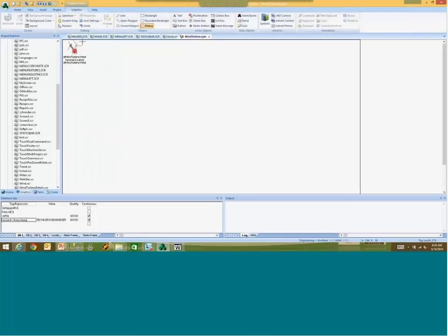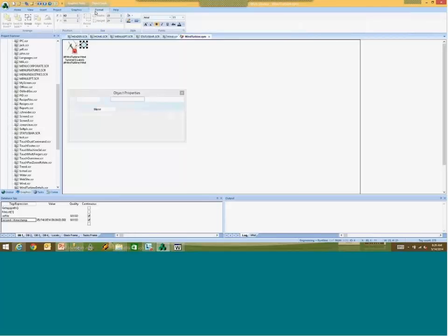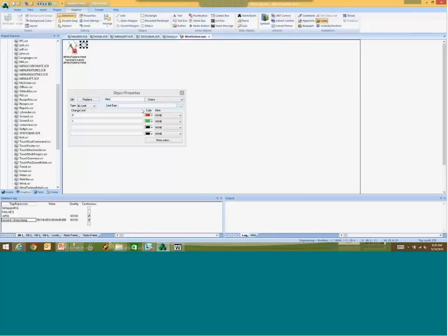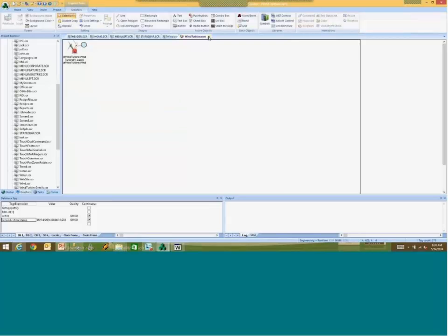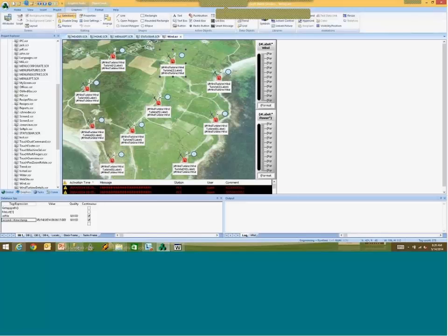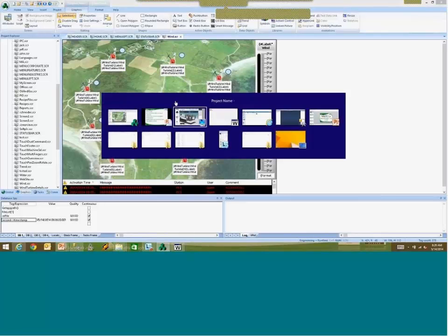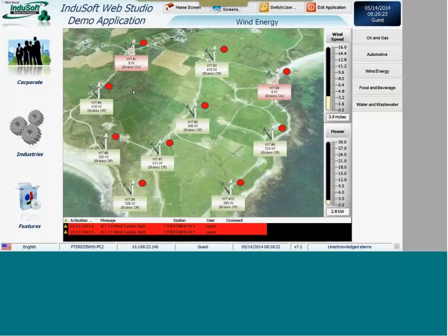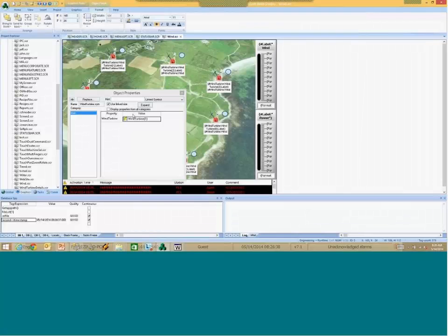And let's do something quick and dirty here, like create this circle and tell this circle to change color according to the tag blink slow, something dummy. Once I change the master symbol, all the instances of this symbol throughout the whole application are updated, and during the runtime, you see that it's functional. So using linked symbols, you have the ability to define the architecture of a group of objects, what's called a linked symbol, use it throughout the application, exposing only the properties that should be different from symbol to symbol.